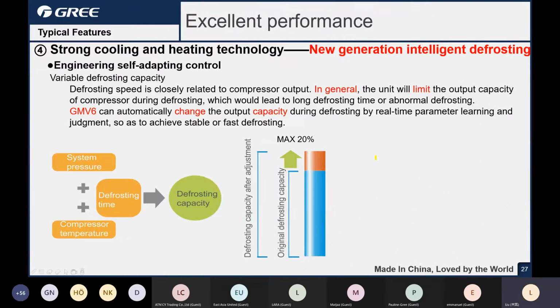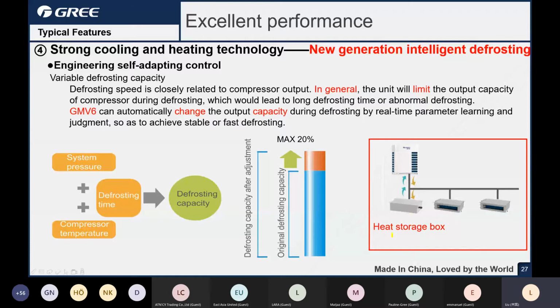And for the defrosting, I already introduced that the unit can change the capacity depending on real-time parameters such as pressure and compressor temperature. Another one for GMV6 is that you can also choose the heat storage box. In heating mode, when the unit starts defrosting, it can absorb the heat stored in this box to do the defrosting, and it will not affect the other regular indoor units running. Okay, that's the heat storage box. That's a lot of choice.